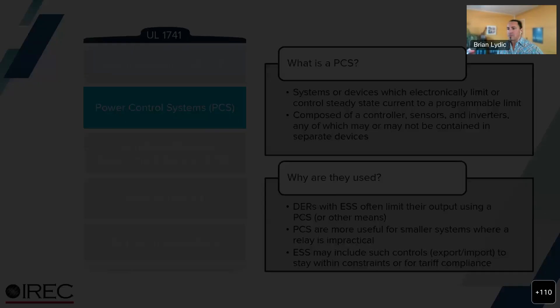Here we've got an example of a power control system, which can be configured in many different ways. As mentioned, this can be multiple pieces of equipment, or you could have a power control system and inverter that's all self-contained. Usually you've got CTs, current sensors, monitoring export. This is the export control use case, rather than the National Electrical Code type of use case, so we're just monitoring export to the grid through the meter on the right. You've got a controller which monitors that current level, the export level, and then connects to the inverters, usually through some sort of communications signal, to control their output.